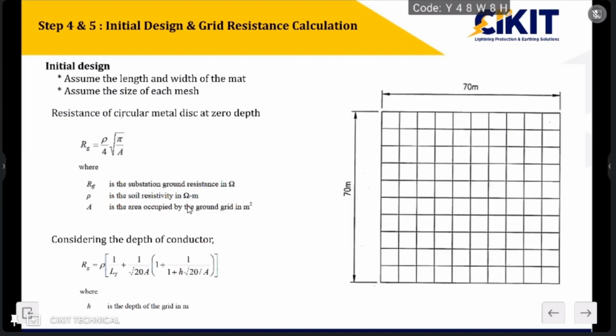Then I have to perform this calculation with 10 meter spacing, calculate the resistance value, and compare those values with the tolerable values. I have to calculate the value of step and touch voltages for this initial design. If the step and touch voltages are within the tolerable limit, then I can maintain the values. If the step and touch voltages are above the values, then I have to reduce the spacing. For example, if I take this value as an example, 70 meters is there.